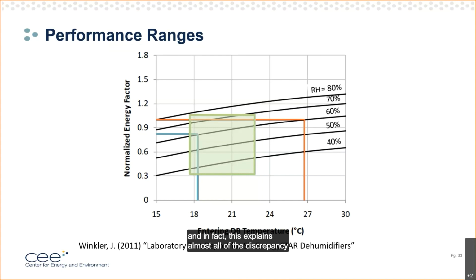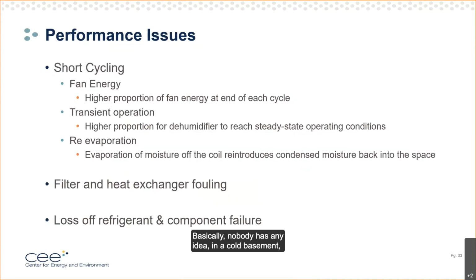And in fact, this explains almost all of the discrepancy between what we measured and the rated efficiency. 70–90% of this performance loss is just the difference in operating point. So this seems really simple, but unfortunately none of this is communicated in the product literature or the retail space, and there's a lot of consequences for that. Basically, nobody has any idea in a cold basement how much energy or condensate should be removed, especially if they're taking guidance from these rated conditions.